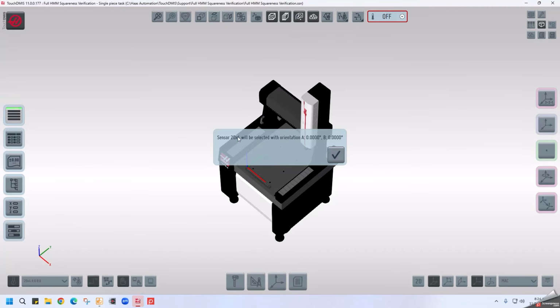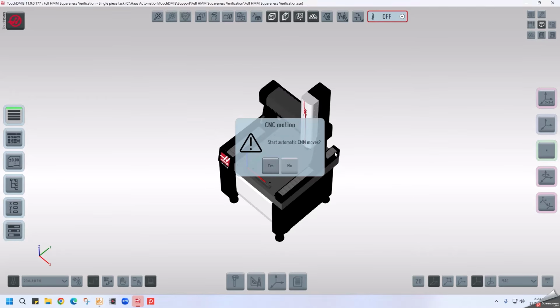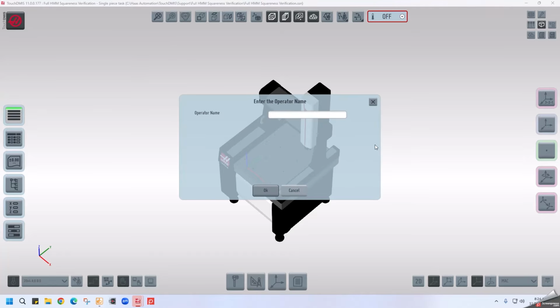Now, TouchDMIS will make sure that I have the 20 by 4mm ruby ball installed on the probe and that it's in the A0, B0 orientation. Then I'll click the check mark. Next, I'll say yes to the automatic CMM moves. Now, I'll input the operator name. I'll put my name as, for example. Now we'll enter the HMM serial number. For example, I'll just put 100 here.